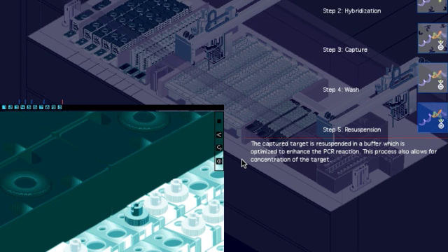That's it. As you see, manual steps are limited to loading and unloading. Prepared patient specimens can be stored or added to the master mix for amplification and detection using the Cobas Amplicor. And the Cobas Ampliprep system meets the automation criteria defined by clinical laboratorians worldwide.